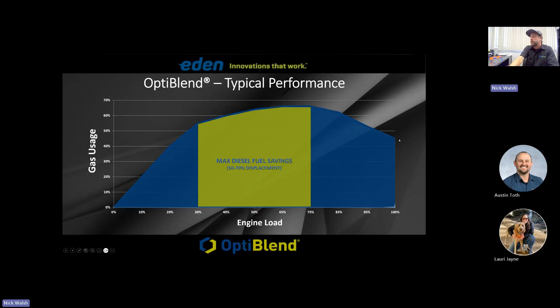As load comes up, we'll introduce more and more gas until we're into the meat of the range—this 30 to 70% engine load is where we get our maximum offset, our maximum fuel savings. As loads continue to increase up to 100%, we start to taper gas off, again for the health and safety of the engine. We want to keep temperatures down—exhaust temperature is going to rise due to the chemistry of burning natural gas versus diesel. So that's what limits us at the top end. Startup: no gas. Then maximum gas, then taper off.